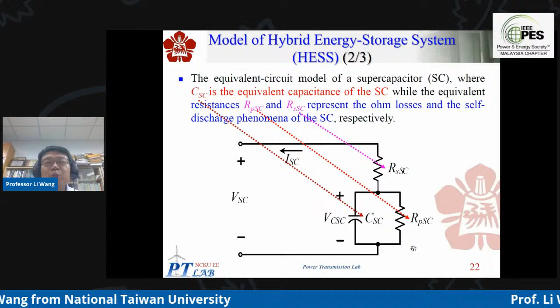With the VRB and our supercapacitor, these two energy storage systems connect through a bidirectional DC to DC converter to our energy storage system, which connects here to the 1200 volt DC link. When energy flows this way, it's boost mode and the energy storage system discharges energy to the DC link. When energy flows the other way, our energy storage system is being charged by the 1200 volt DC link.